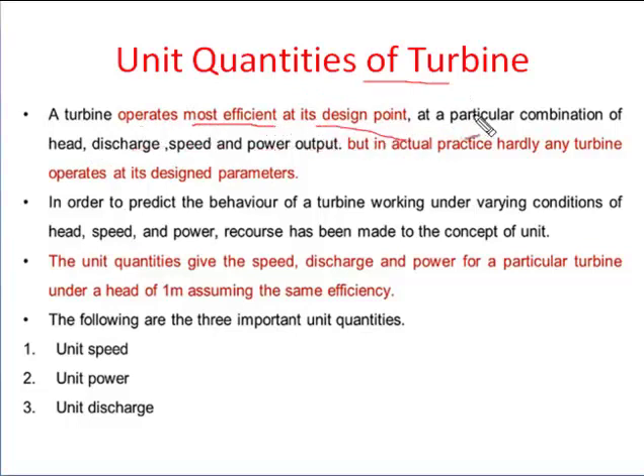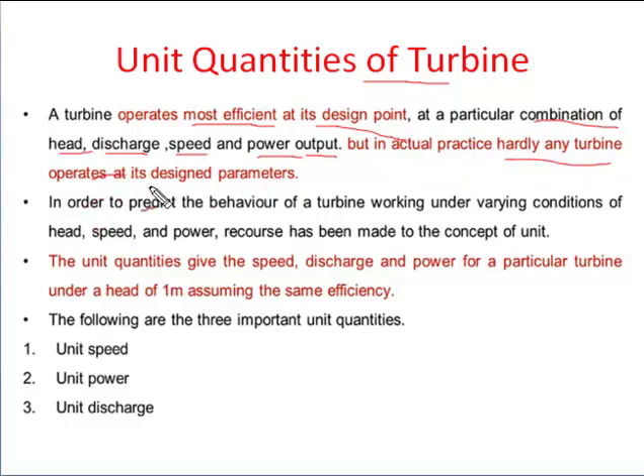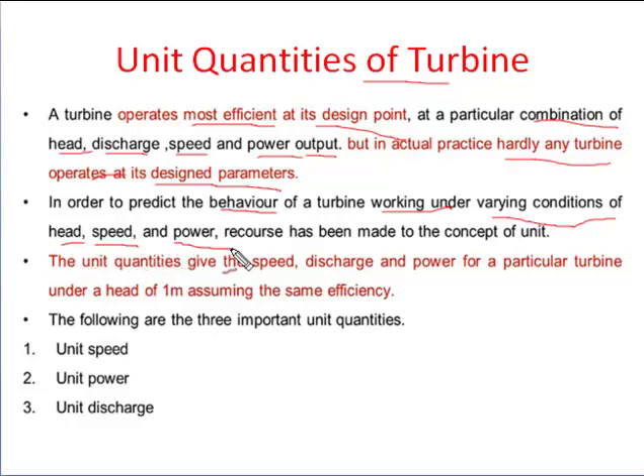A turbine operates most efficiently at its design point at a particular combination of head, discharge, speed, and power output. But in actual practice, hardly any turbine operates at its design parameters. In order to predict the behavior of a turbine working under varying conditions of head, speed, and power, recourse has been made to the concept of unit quantities.